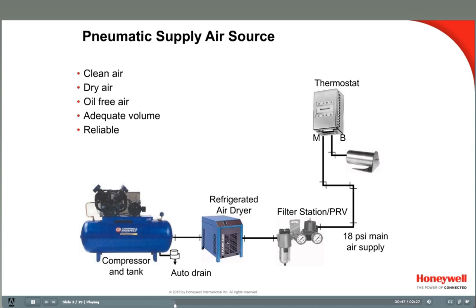Airborne particles and oil mist can cause problems in a pneumatic system. Particles can block air flow, and when oil collects in orifices and small passages, it can foul equipment and shorten its life. To remove oil mist, an oil coalescing filter is used. These usually have a drain at the bottom of a glass bowl and will need service once solid particles plug up the filter. Usually an increase in pressure drop across the filter indicates that the filter element needs to be replaced.